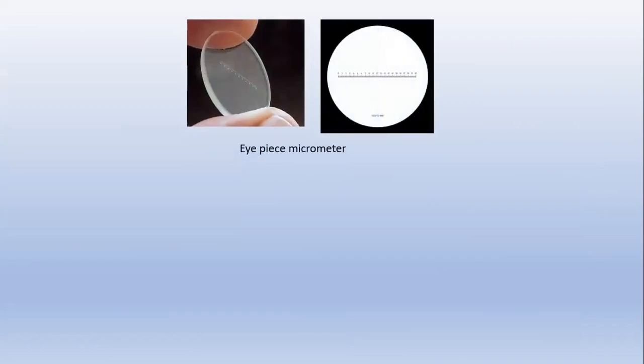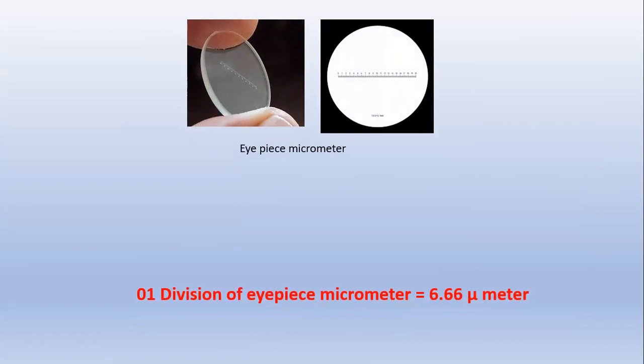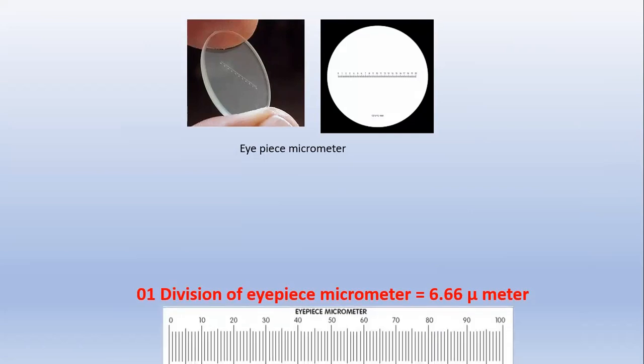We are going to use this calibration — when measuring a particle, we just multiply the number of eyepiece divisions by 6.66 micrometers to get the actual size. In this way we perform the calibration of the eyepiece micrometer. A practical demonstration will be given in the next video. If you like this video, please subscribe to my channel and give a like. Thank you.